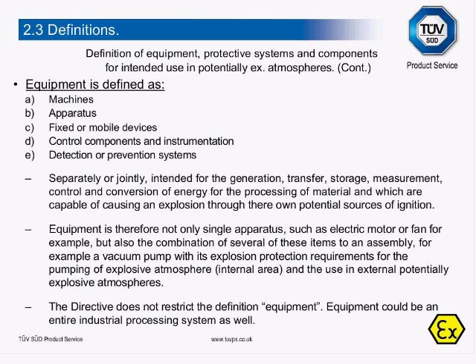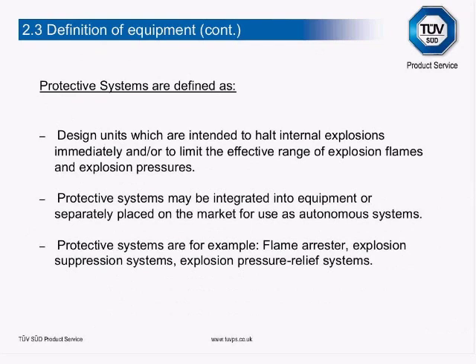Equipment is therefore not only single apparatus such as an electric motor or fan, but also a combination of several of these into an assembly — for example, a vacuum pump with its explosion protection requirements for the pumping of explosive atmospheres and use in external potentially explosive atmospheres. The Directive does not restrict the definition of Equipment; equipment could be an entire industrial processing system as well. A protective system is defined as design units intended to halt internal explosions immediately and/or to limit the effective range of explosion flames and explosion pressures. Protective systems may be integrated into equipment or separately placed on the market for use in autonomous systems — for example, flame arrestors, explosion suppression systems, explosion pressure relief systems.